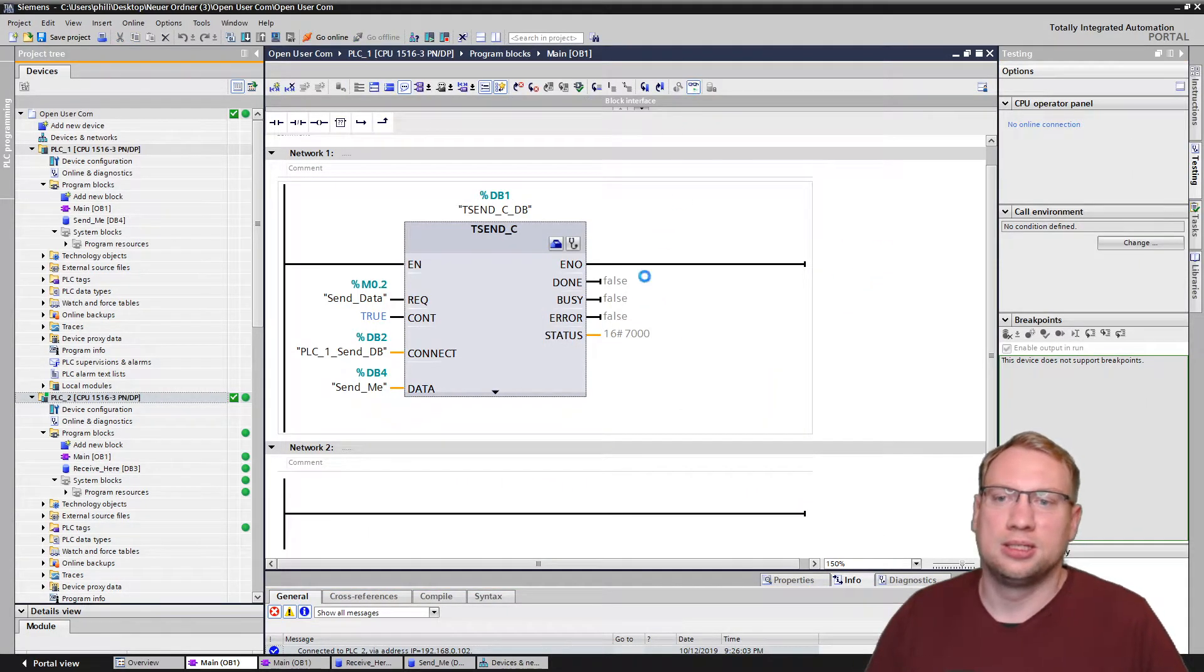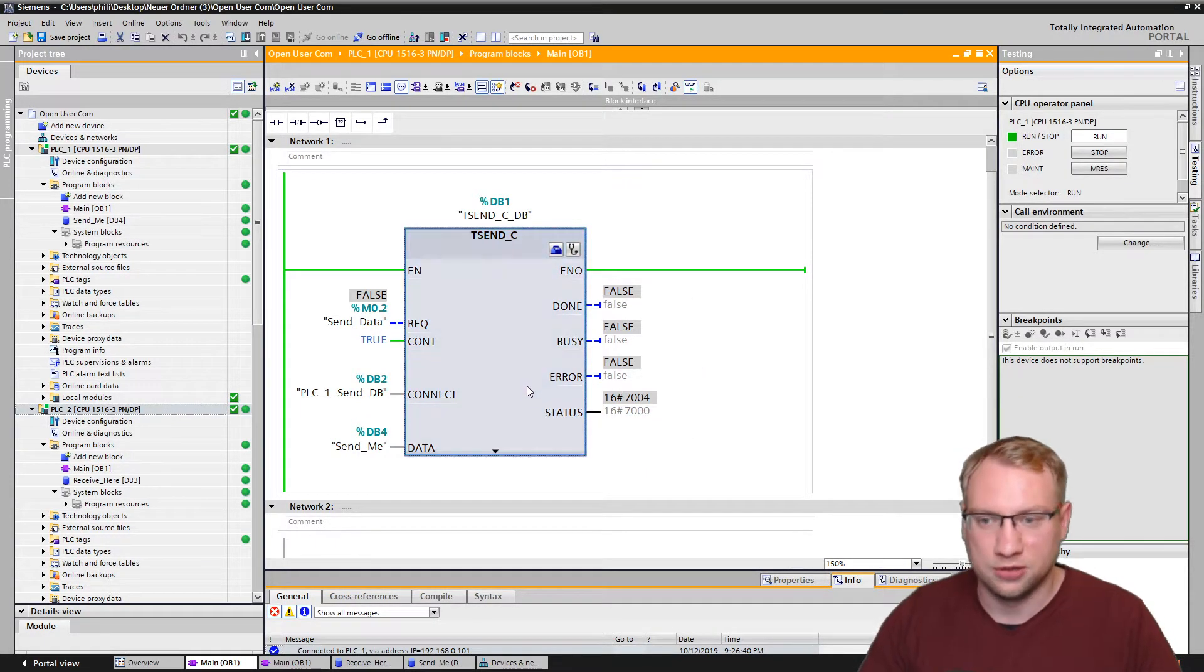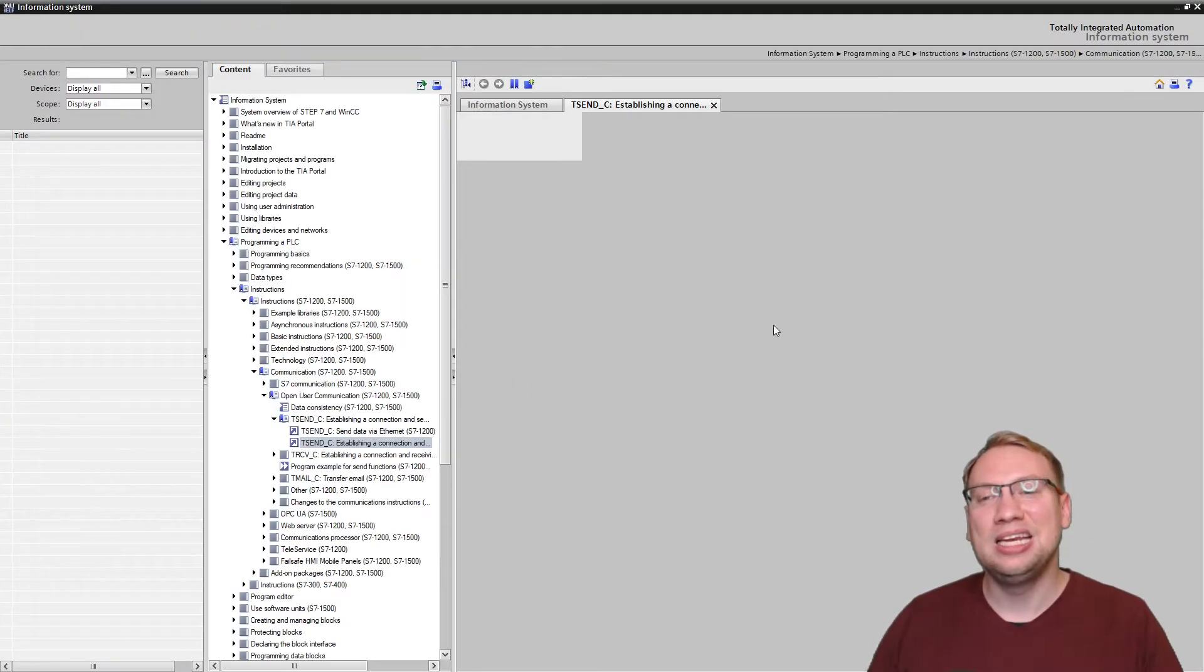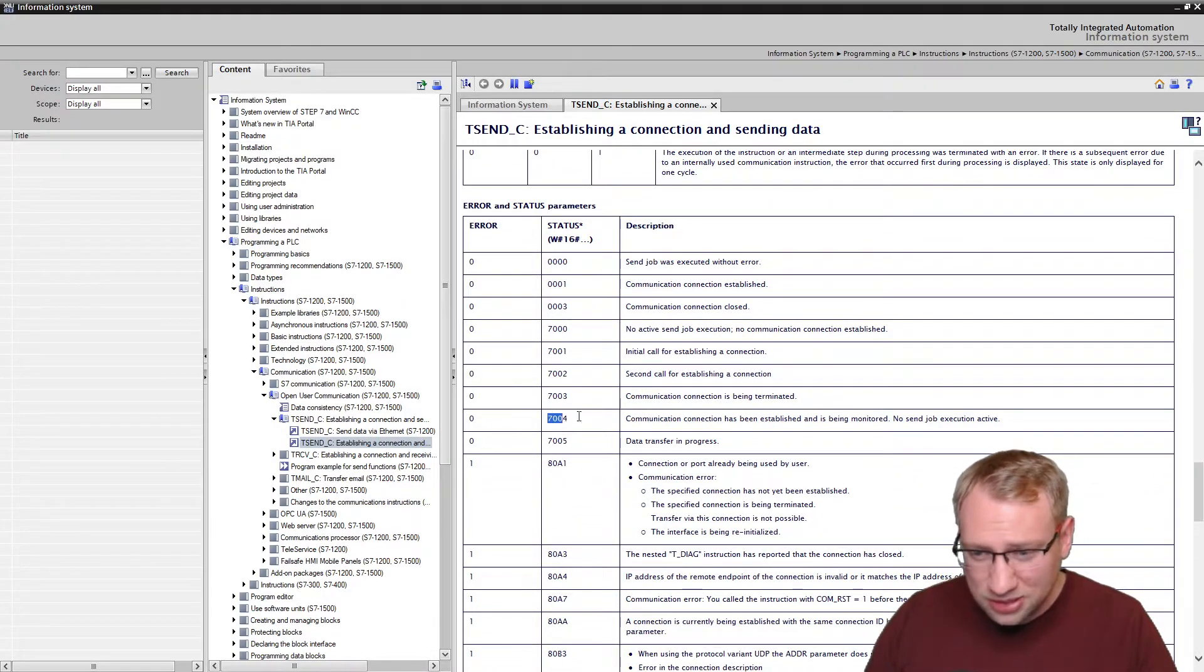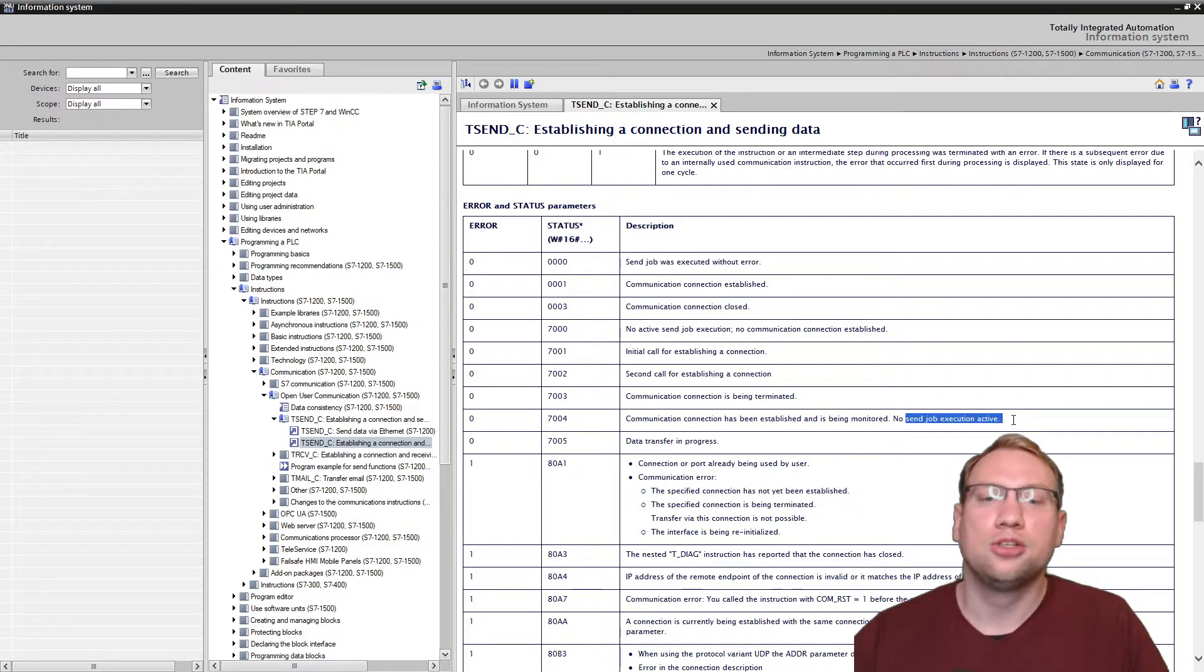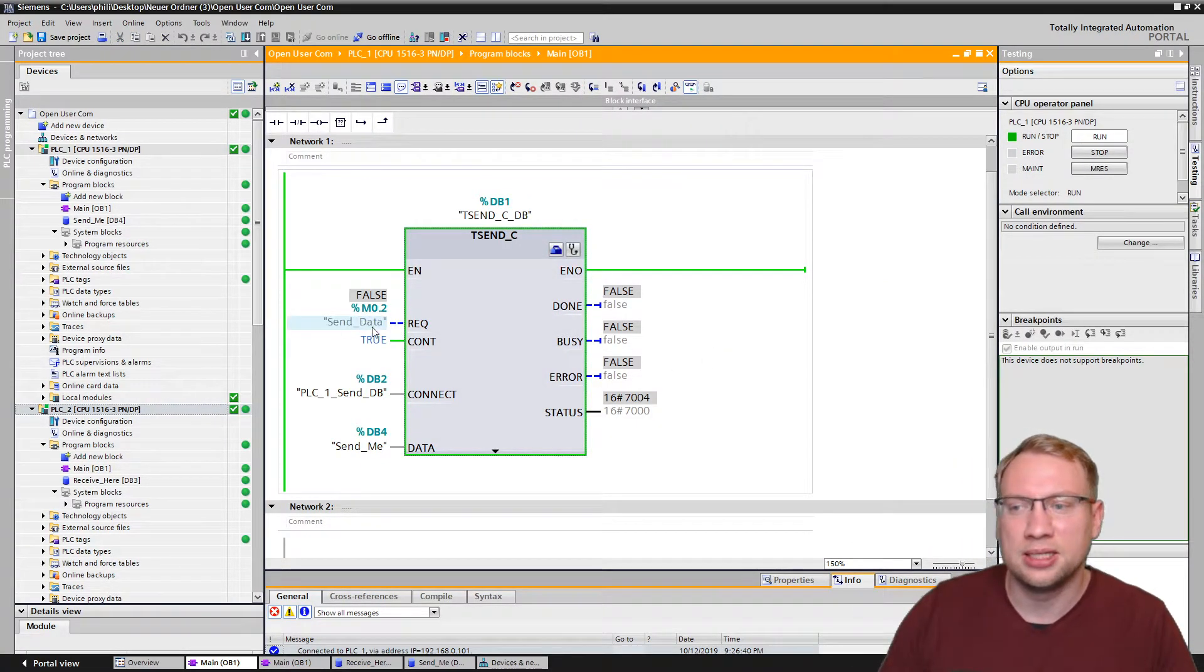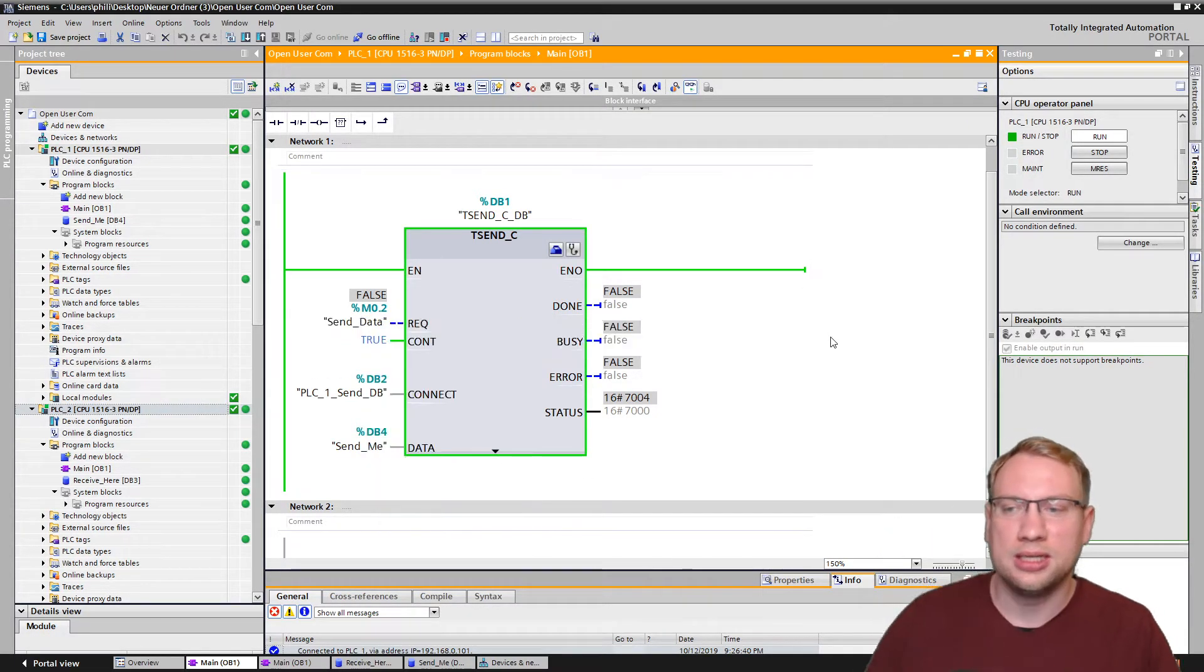First PLC, let's see. Now that the connection is there, you see it's not changing this value anymore. It says 7004. So let's check it out. What does 7004 or 7004 hex mean? 7004 hex communication connection has been established and is being monitored. No send job execution is active. Make a guess. No send job execution. We are only sending data on a rising edge of send data. So if I now modify this to one, we will send data.